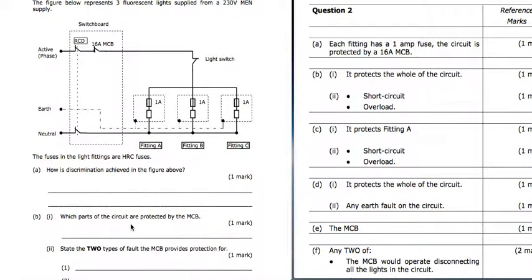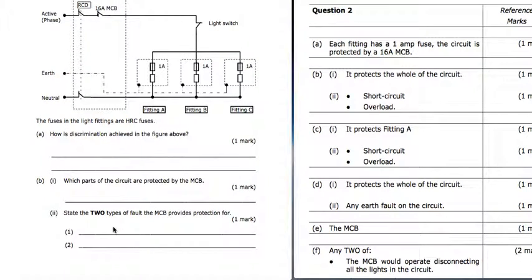Which part of the circuit are protected by the MCB? So it protects the whole of the circuit. So that 16 MCB is protecting all 3 fittings. State 2 types of fault the MCB provides protection for. So it provides protection for short circuit, which would be the magnetic thing inside the MCB, and overload, which would be the thermal bimetallic strip. So the 2 things, short circuit, overload.